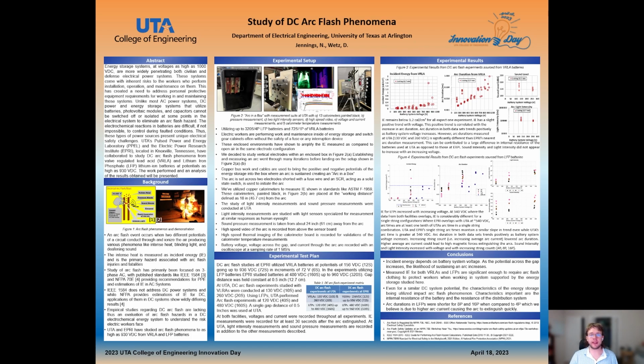The measurement suite and setup shown to you today at UTA is one that simulates and emulates the environment that an electric worker will be performing their work and maintenance in. These energy storage systems employ switchgear cabinets or distribution boxes that do not have the protection of, say, a fuse or current interrupting device. As well, IEEE 1584 notes that enclosed spaces in a vertical electrode configuration, quote, amplify the incident energy release, meaning that a comparative open air arc in a similar electrode configuration has less incident energy measured than one studied in an enclosed environment.